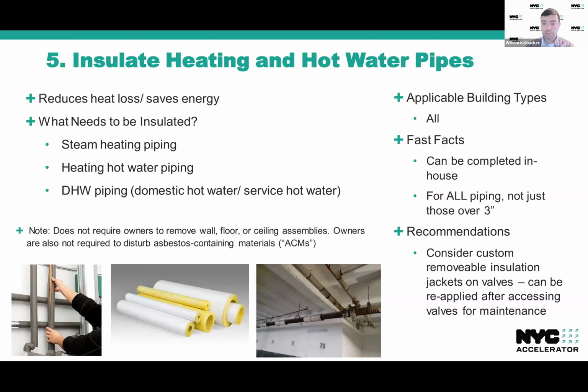Just a general best practice and recommendation is to consider custom removable insulation jackets on larger system components that you might need to access for maintenance. It might make a lot more sense to get something custom that can be put on and off, so that you don't have to ruin your installation job every time you need to adjust something or fix something on the system.